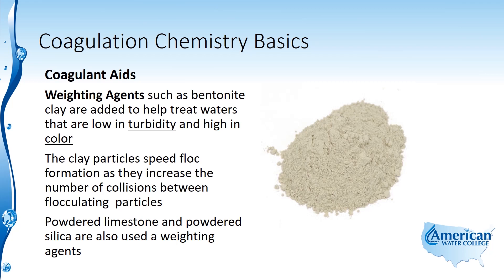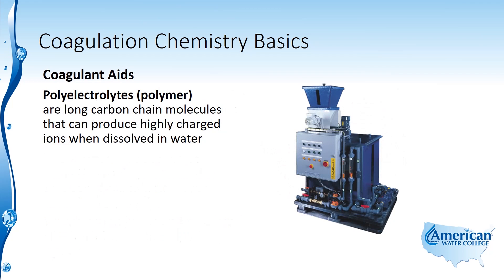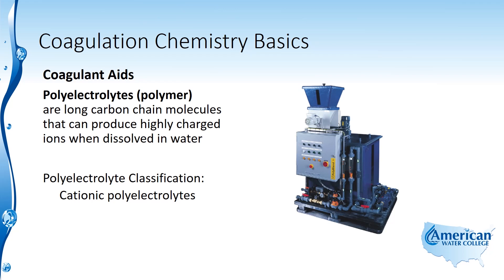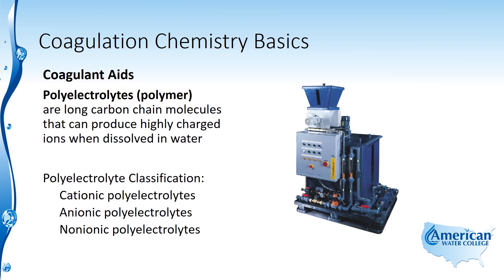Poly electrolytes, also called polymers — more commonly called polymer by operators — are long carbon chain molecules that produce highly charged ions when dissolved in water. They are classified according to their charge. Cationic poly electrolytes produce positive charges when dissolved in water. Anionic poly electrolytes produce negatively charged ions when dissolved in water. Non-ionic poly electrolytes, despite the name, release both positive and negatively charged ions when dissolved in water, so the charges effectively neutralize one another.